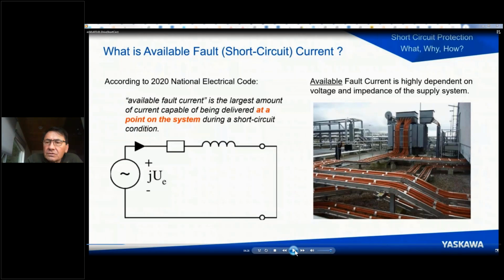One note here is that it is the installer's responsibility to determine the available fault current so that he can ensure that the SCCR rating of all of the equipment he is installing exceeds the available fault current. If he does not do this, there are some pretty significant liability issues associated with it. It is not the responsibility of the end user customer, be they an industrial plant or an individual on a winery, to determine and let the installer know that. If the installer is certified, and under the California code, that means he's got a contractor's license, a C10, I think it is, for electrical, he's been trained to understand the methods of determining what the available short circuit current is. Available fault current, again, is the responsibility of the installer.